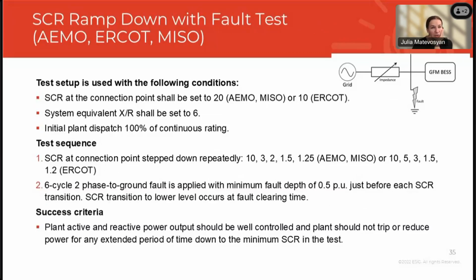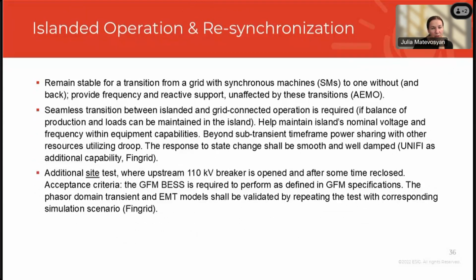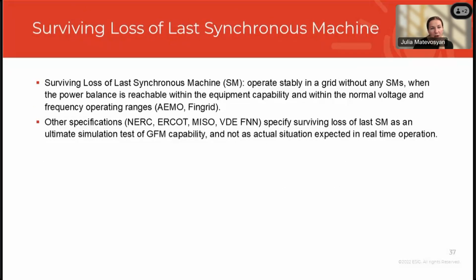There are also tests for short circuit ratio. So basically, to ensure that the grid forming resource can operate stably at different short circuit ratios. There is a test that's defined by AEMO, ERCOT, and MISO. And again, you can look at it. Islanded operation: again, stable operation is required when being part of an island without any synchronous machines and then reconnecting back to the grid.